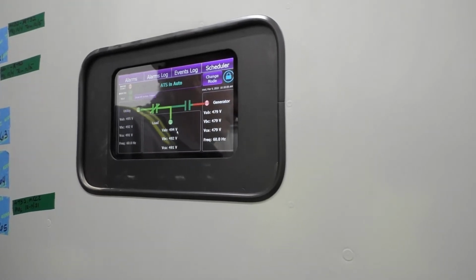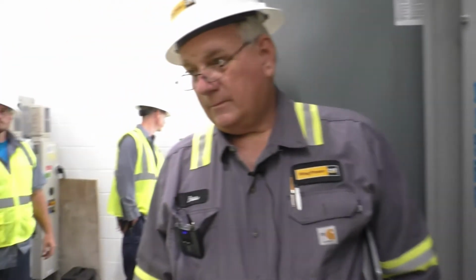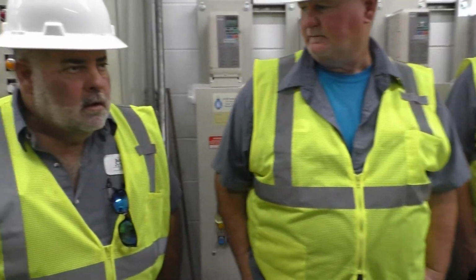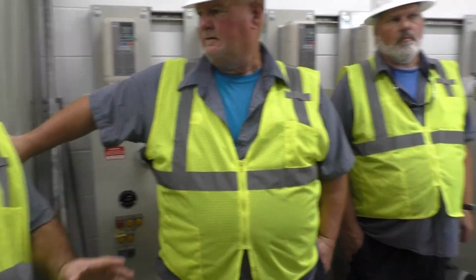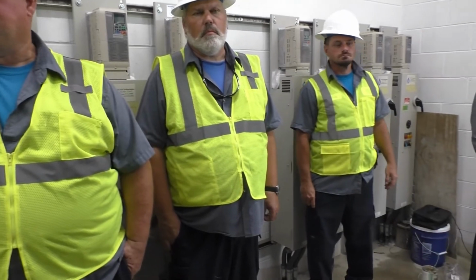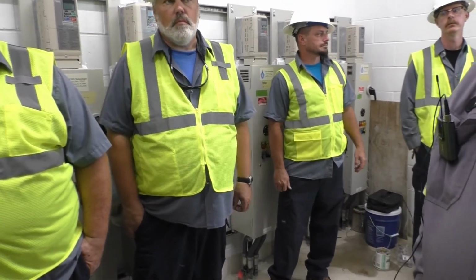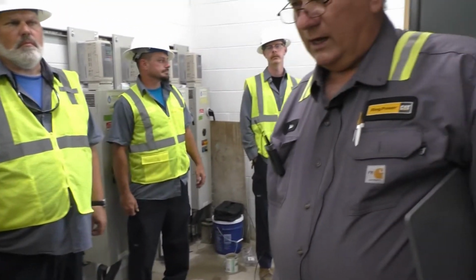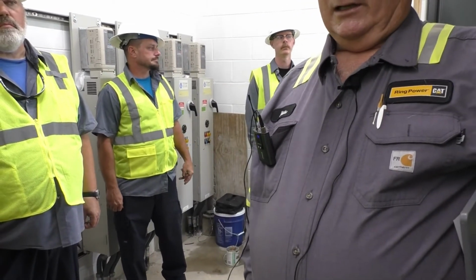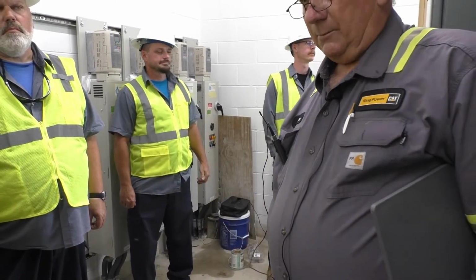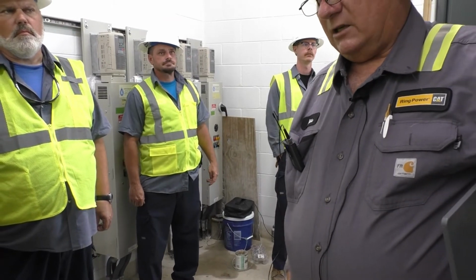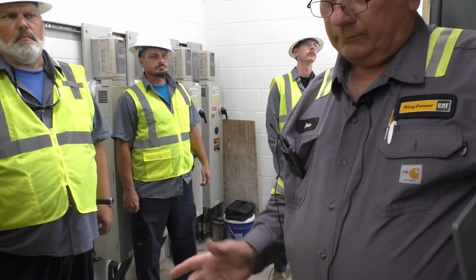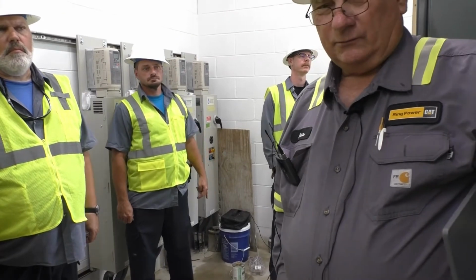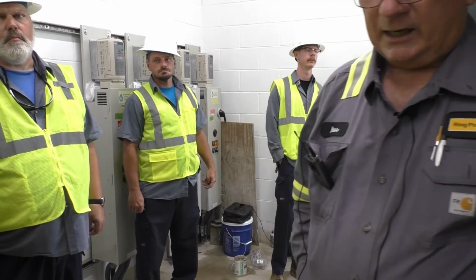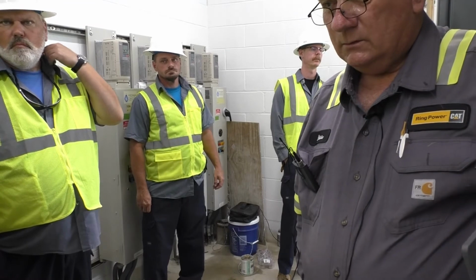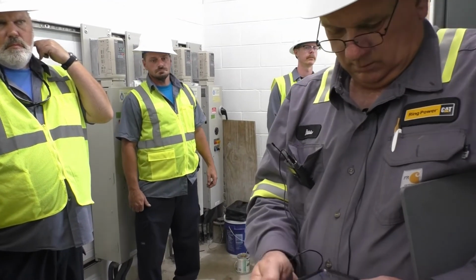Oh, what did you say the burn rate on fuel is? 58 gallons at 100% load per hour. 58 per hour. At 100%. The capacity of the tank is, usable, it's 6,293 gallons, but usable is a little under 6,000. You get about 90% capacity because you can't fill it full and you can't pull it to the bottom. So 90% of whatever that is, it's in the 5,000s range. But it's a lot of fuel. I think it's in the mid-5. Yeah, I can tell you mid to upper.